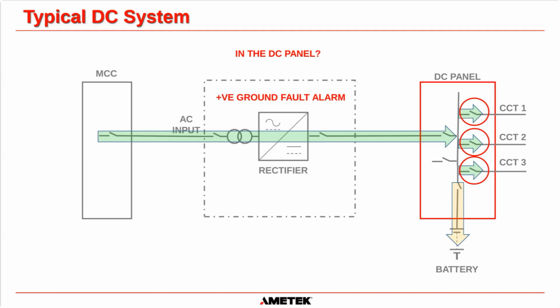If you open all of these circuit breakers and the ground fault goes off, we now know that it's either in circuit one, circuit two, or circuit three. It's in the load circuits, okay? So we're really getting somewhere now. We've ruled out four places where it could be. So the last thing is, is it on the load circuits? Obviously, yes. We have to find out which load circuit it is.